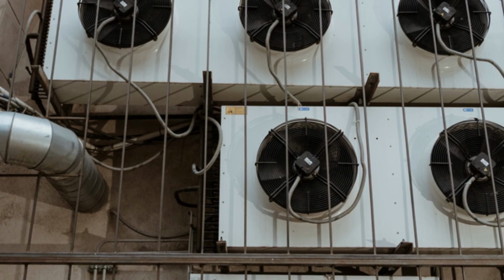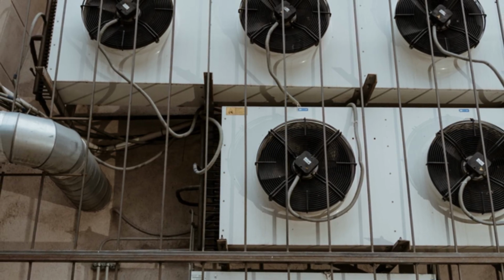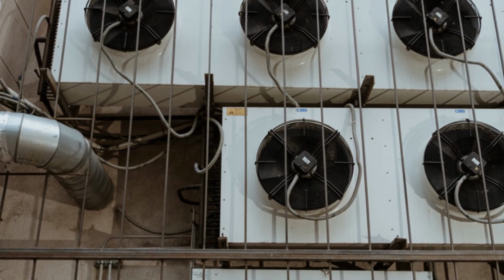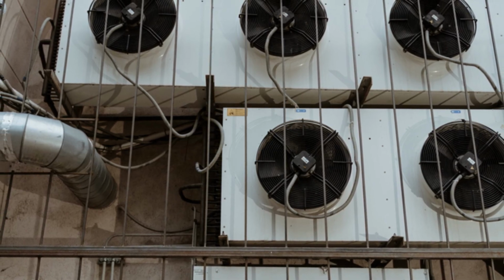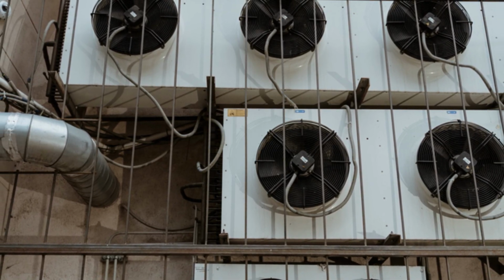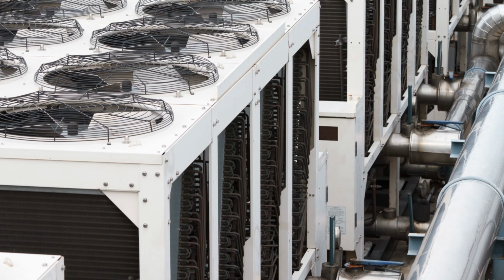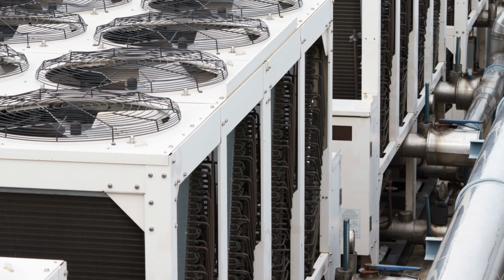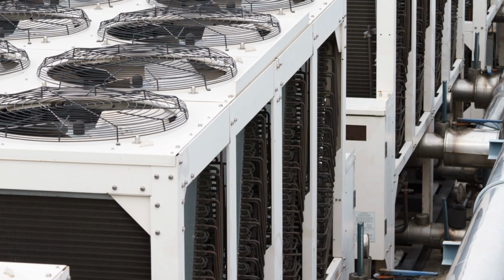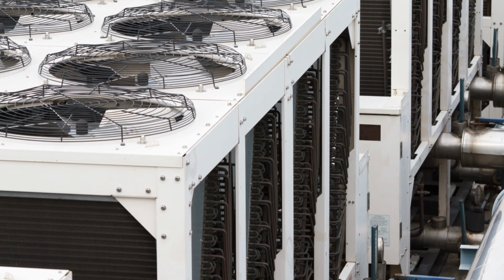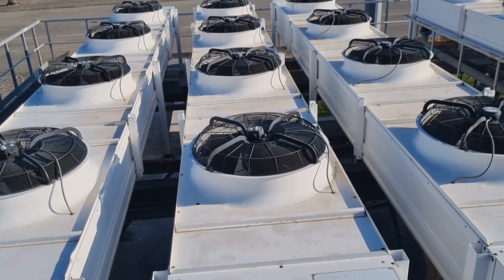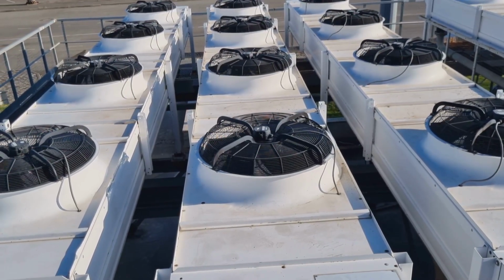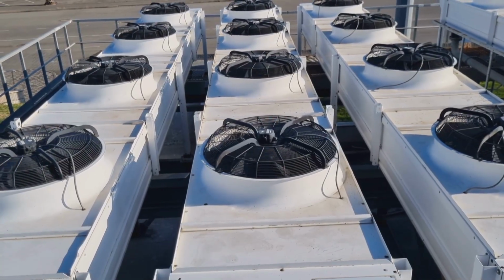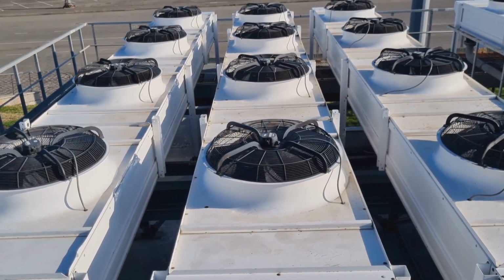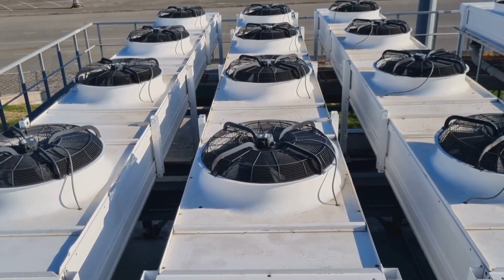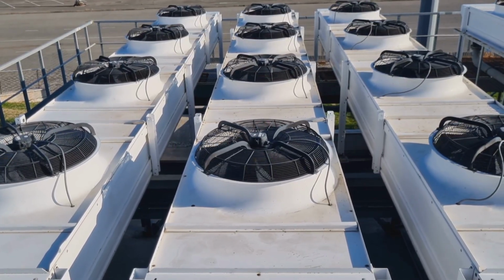Another important method is evaporative cooling. When water evaporates, it carries heat away. That cooling effect can reduce the amount of electricity needed for mechanical cooling. But there is a trade-off. When water evaporates, it is consumed. It leaves the system as vapor. So, a data center using evaporative cooling may use less electricity for cooling, but more water. A data center using mostly mechanical cooling may use less water directly, but more electricity.